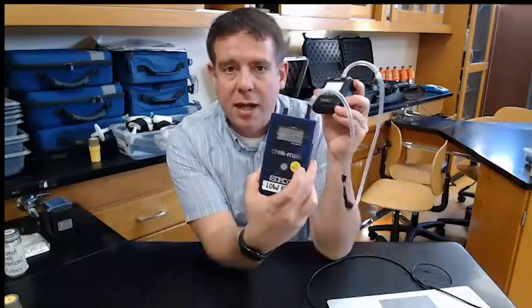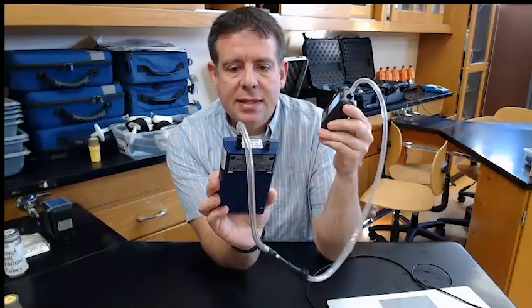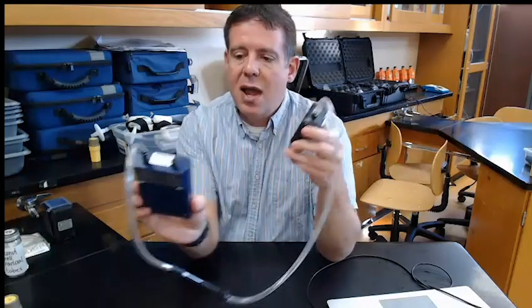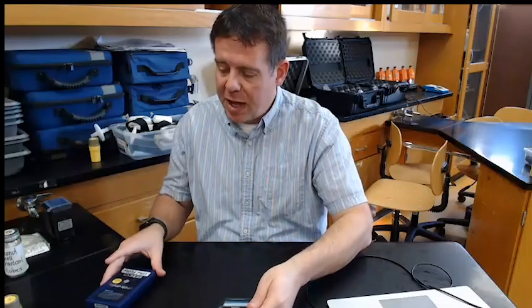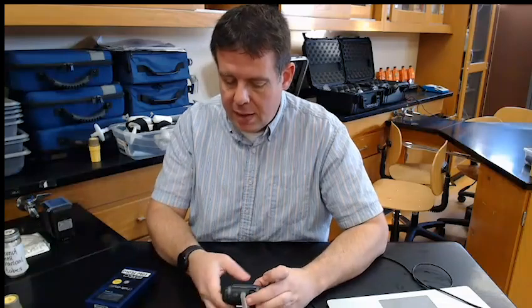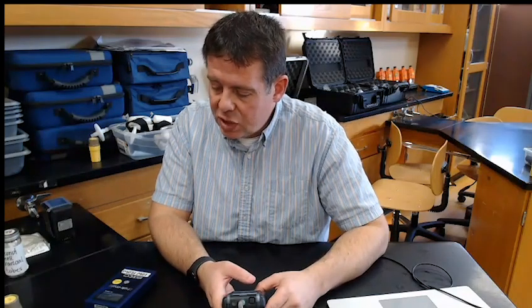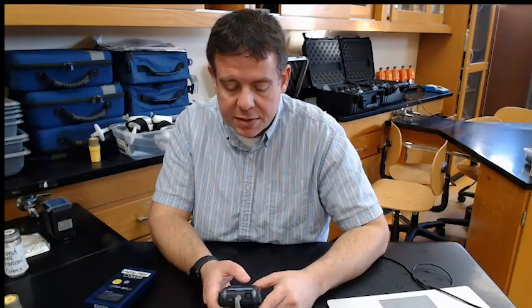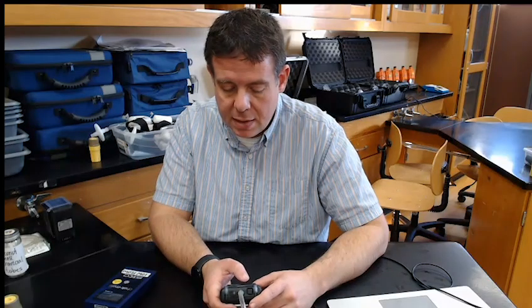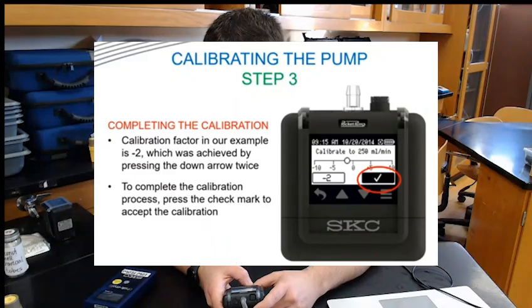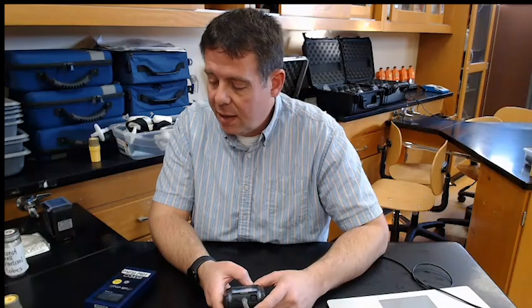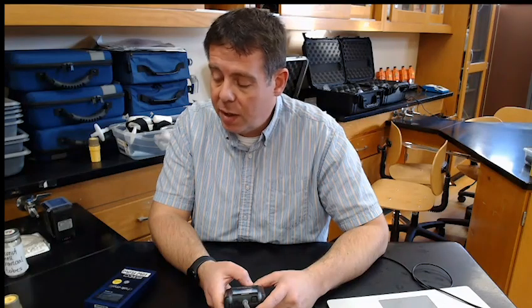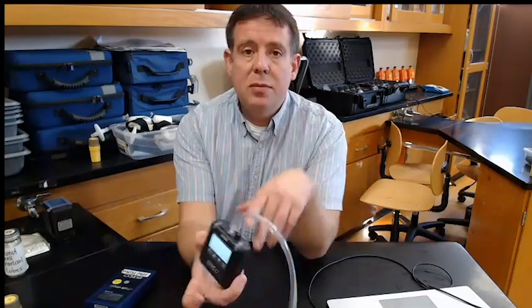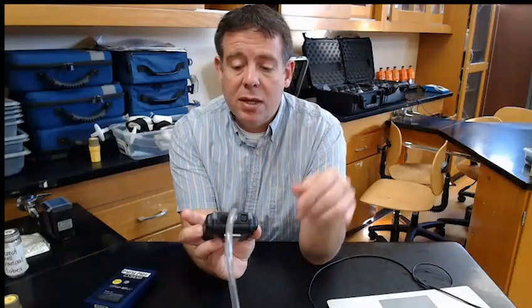So we have 200 right now. If we compare it to the chek-mate right now, it's going up and down. So we're going to give it a minute to stabilize, but we're almost at 200 milliliters. Right now we're at 197. So we'll give it a minute because I feel like it's bouncing around a little bit before we adjust it. So it looks like we need to adjust it by about 2 milliliters. So not very much here. I just hit that arrow key once, and it's at 199.4. Oh, it jumped up to 2. So just letting it stabilize for about 30 seconds here, because we're right on the money, about 198. And then you'll hit that bottom check mark when you have it. So we didn't have much of an adjustment, just a plus 1 really. So not much at all.